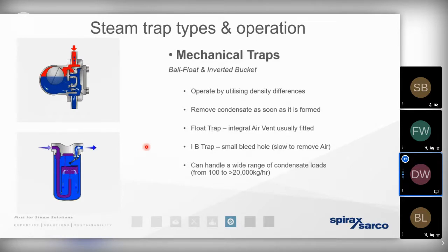The main difference between the float and the inverted bucket is that the float trap, in the vast majority of cases, will contain not only that mechanical valve, but it will also have a secondary thermostatic valve. So that means it will bleed away a significant amount of air that is present whenever the system is starting up from cold. But we've also got a secondary thermostatic valve, meaning that the trap's got a greater capacity when that condensate is cold. The inverted bucket trap is very, very well placed because it can stand up very well to water hammer or a poor condition of steam, whereas the float trap isn't necessarily able to do that.